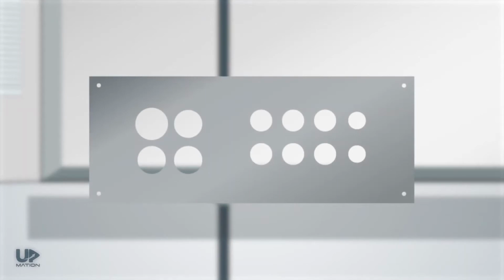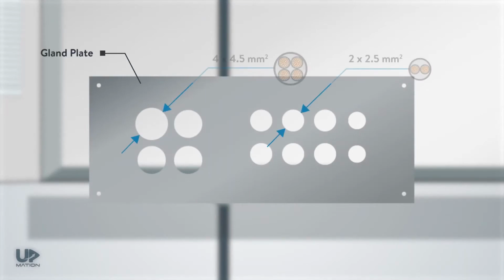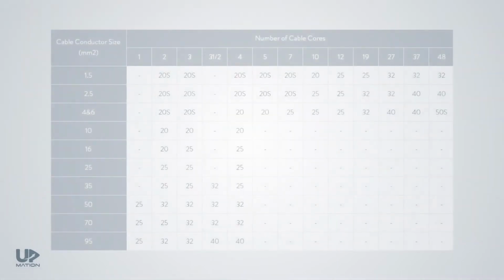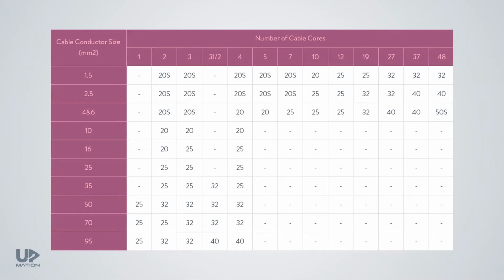To state the obvious, the size of the holes we should drill on the gland plate depends only on the size of the cables we're going to bring into the panel. Accordingly, the cable size will determine the appropriate cable gland size. As you see, there are standard charts for this purpose.